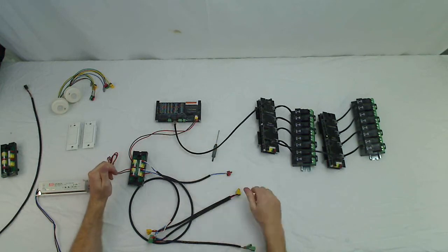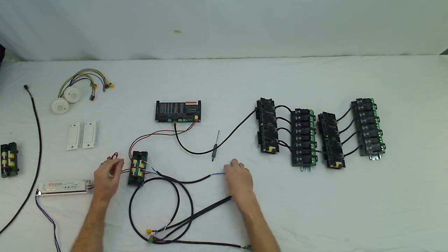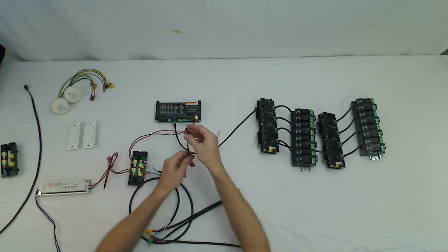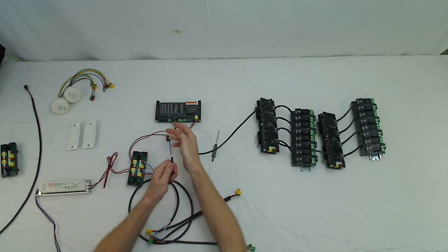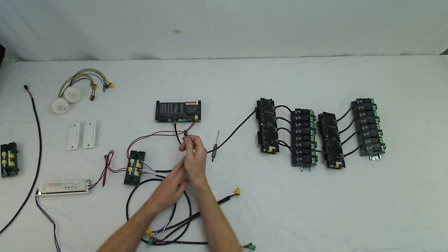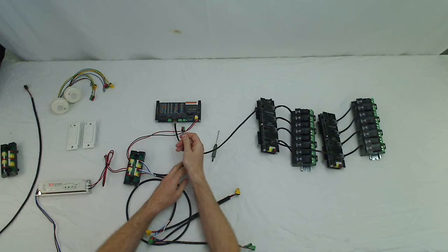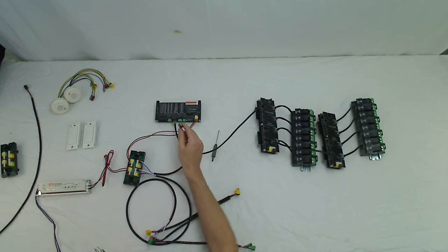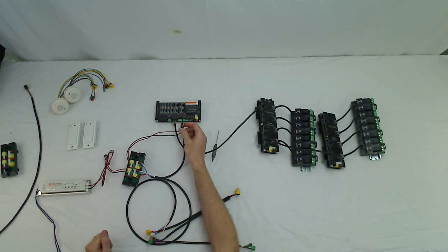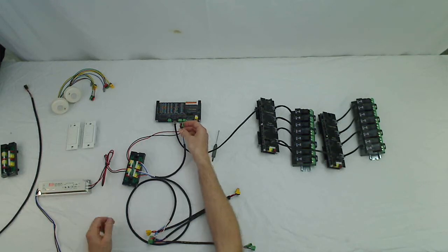So we'll move on to the smart switch network. Our smart switch network is a smart switch port here. And it's a three wire RS485 connection. Green, black, red. Red being positive, black negative, and green is the shield or ground wire.